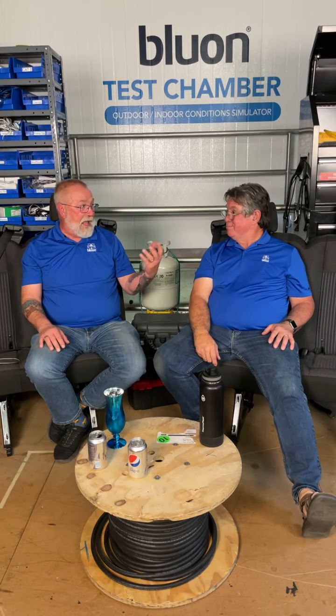And at that point, because you don't have to go back down to the thermostat, now you can take out your jumpers, disconnect the thermostat wires, and now you can jump and see if your problem is between the unit and the thermostat. Because what really is a thermostat? A thermostat is simply a temperature controlled switch. That's all it is. And the thing is, people make them fancy though, because you can.